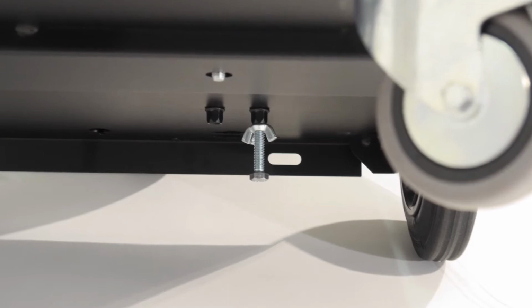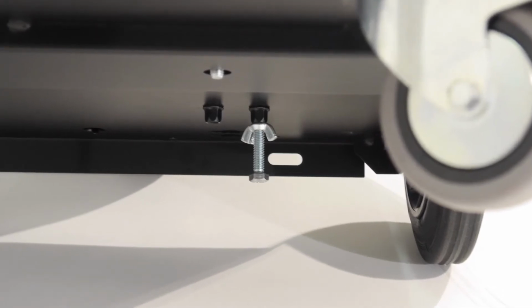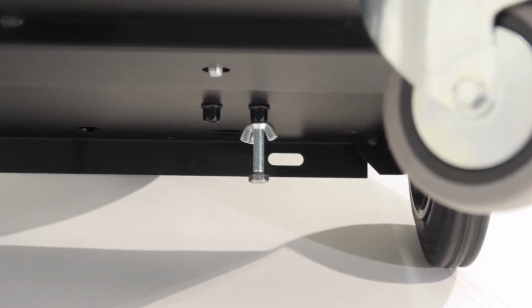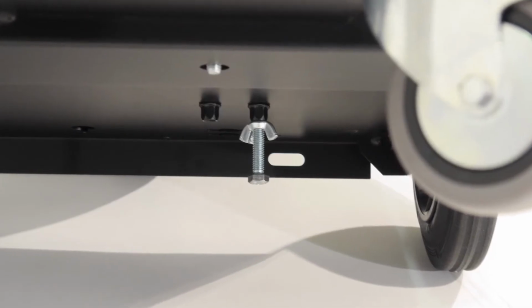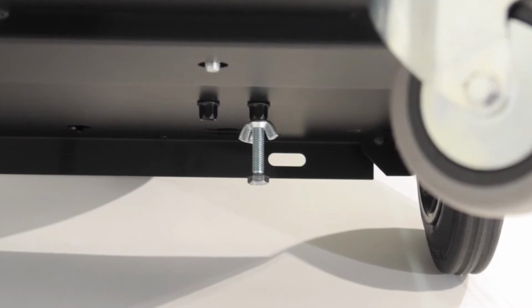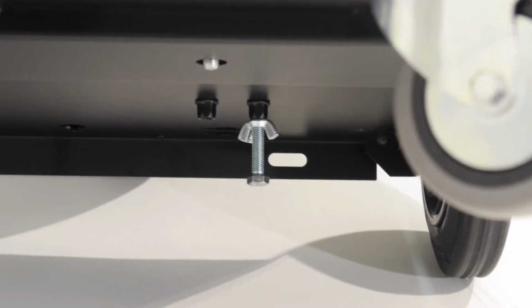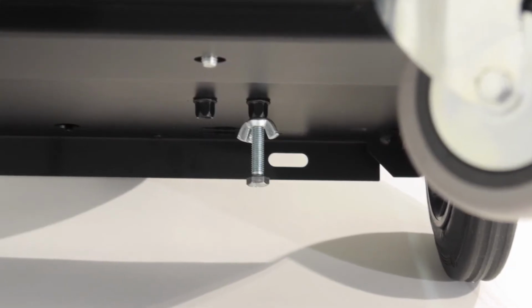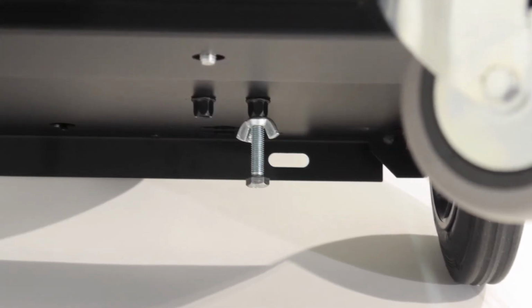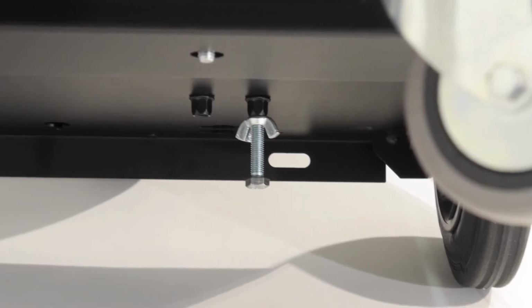Removing the refrigerant load cell set screw, we'll find a bolt with a wing nut on the bottom of the machine. All you need to do is loosen the wing nut and remove the bolt, and that will free up the load cell for the commissioning of the machine.